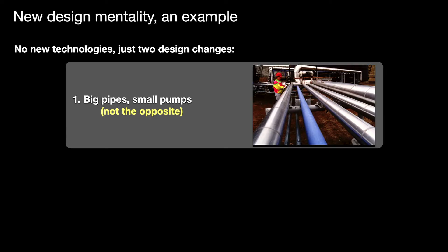Now, the second shift in design is even simpler and therefore harder. That's to lay out the pipes first, then the equipment, not the other way around. Traditionally you put the tanks, boilers, and so on in convenient or arbitrary or traditional places, and then call in the pipe fitter and say, please connect point A to point B.